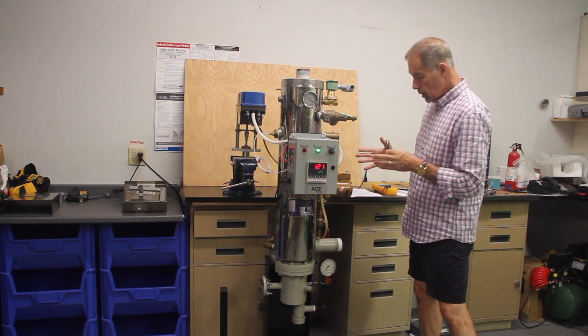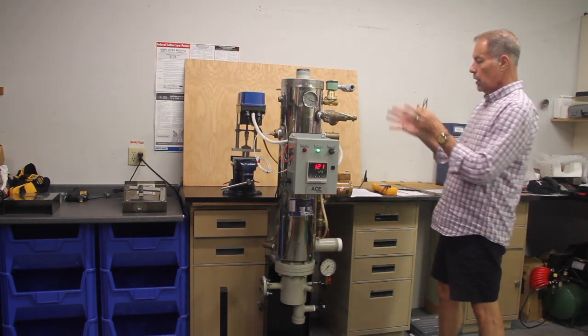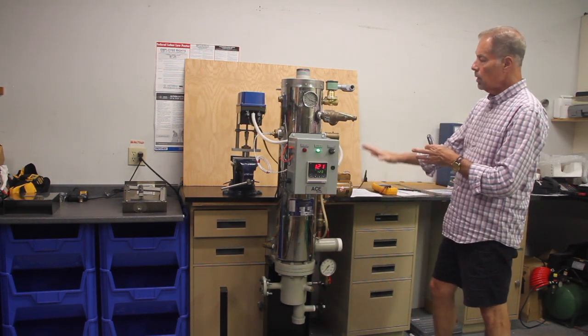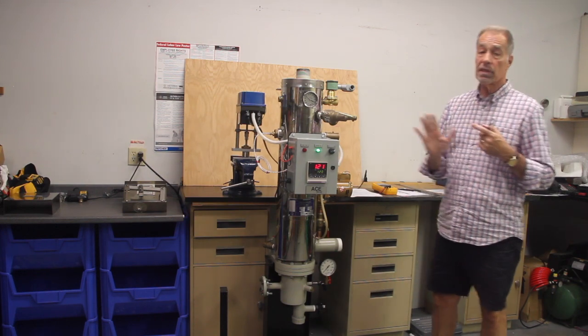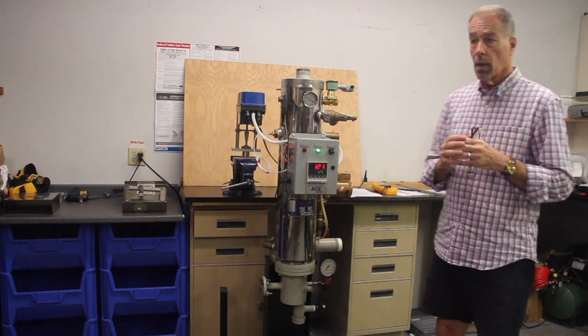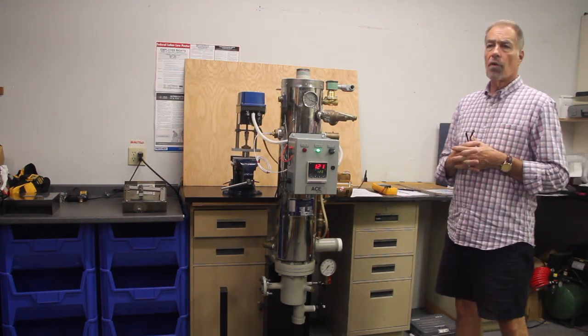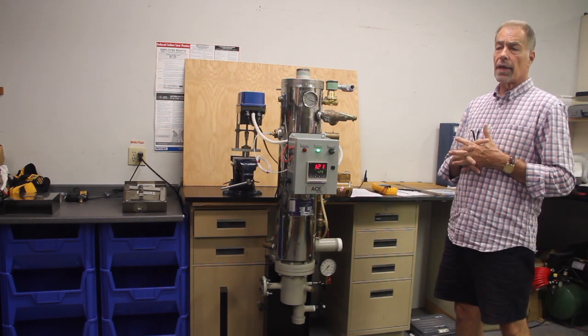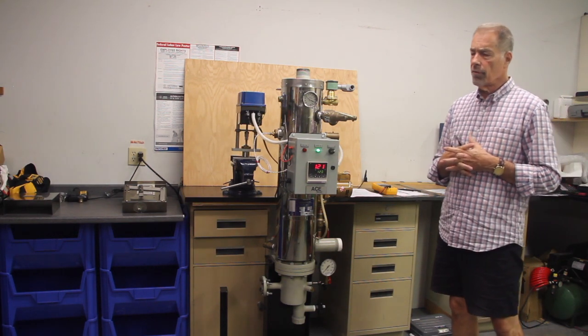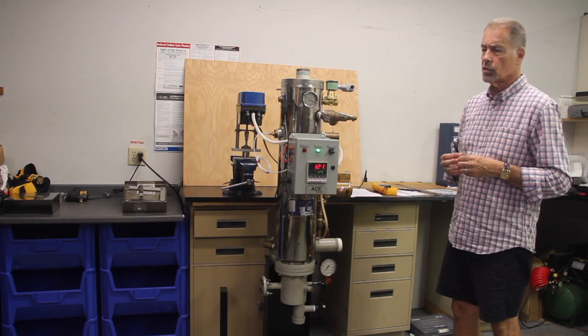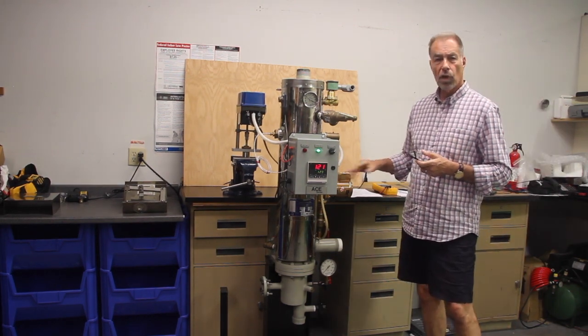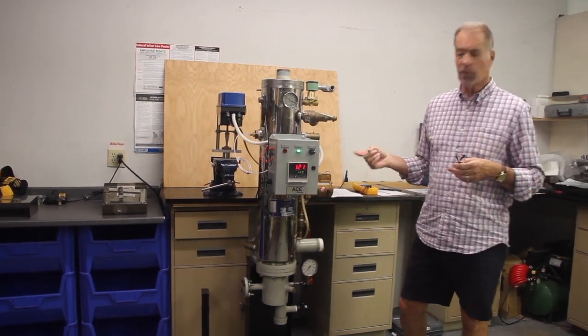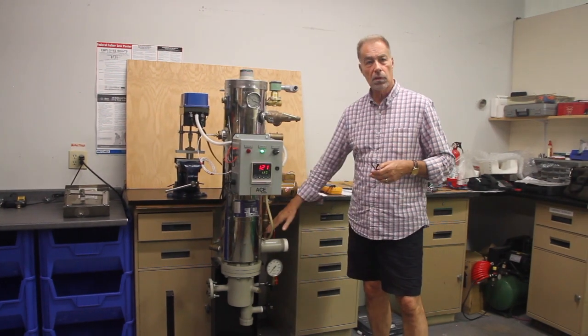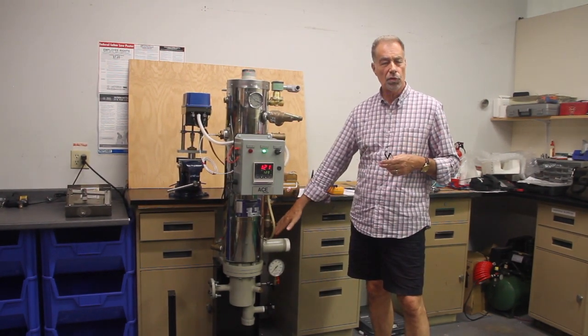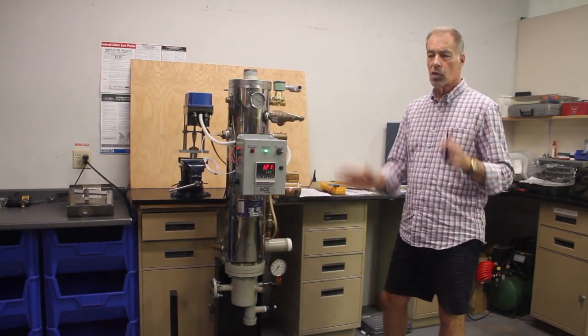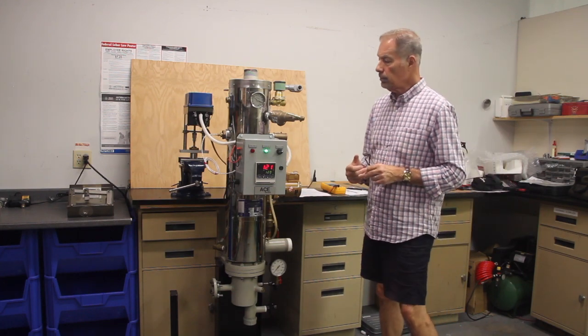So, heater, connection, accessory items, pump, which by the way, we use now a Taco 007 pump. You can use a 005. I've had situations where people have had very, very hard water, very high grains of hardness, and the 007 runs with too much velocity, and they wear out some of these elbows on the pump circuit. If that's happening, just drop it to a 005 and you'll be fine.